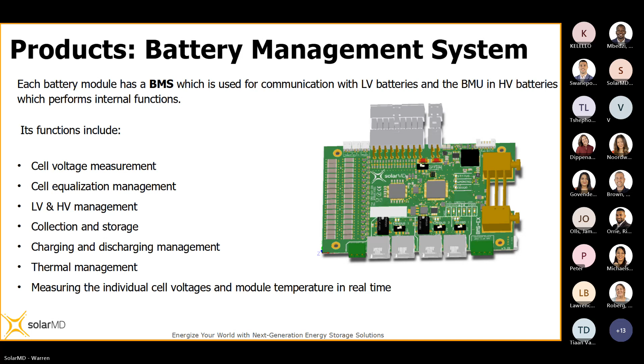Let's carry on, looking at the picture of the BMS to give you an idea of what you're looking at. On the far right hand side is the shunt, which does the current measurements. On the bottom of the BMS you'll see four network ports - they look like network ports, RJ45 or LAN connectors, the kind you'd see on the back of your router or an Ethernet switch. But these are actually CAN bus ports, a common means of communication between equipment of this type. The two ports on the far left are used for communication between multiple SolarMD batteries and our logger. The two ports on the right are used for communication between the batteries and inverter.